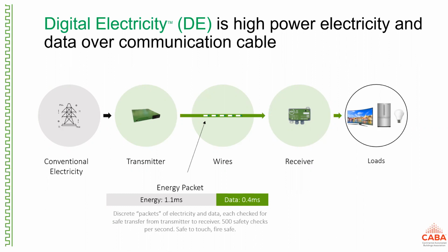Yes, I just wonder about the transmission media, what's the actual wire when you talk about wires? Is it copper? You can't do it on fiber optics, can you? No, we transmit on common communication cabling. Like Cat5? Well, Cat5 is a little thin for us. Usually it's 18, 16, or 14 gauge most commonly—18 to 14 gauge communication cable that you would know is in a building, sometimes called CMP or CMR rated cable.